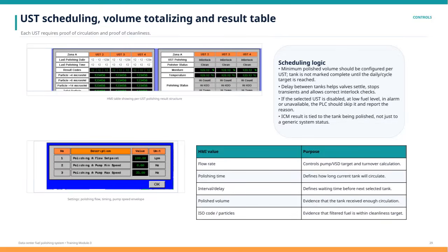Let's take a closer look at the UST scheduling, volume totalizing, and the result table. Each underground storage tank, or UST, must have proof of both circulation and cleanliness to ensure proper maintenance and fuel quality. The controls include an HMI table that displays polishing results for each UST individually. This table shows key parameters like flow rate, polishing time, interval or delay between tanks, polished volume, and cleanliness indicators such as ISO codes and particle counts. These values are critical because they guide the pump and variable speed drive targets, define how long a tank is polished, the wait time before switching tanks, and provide evidence that the fuel meets cleanliness standards.